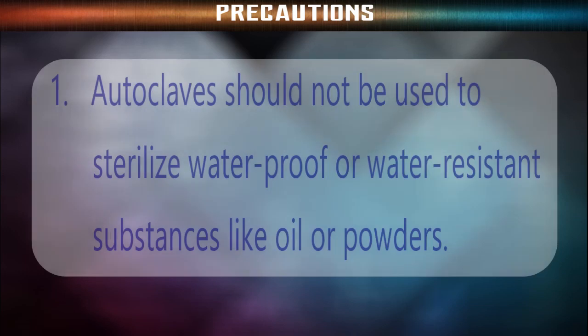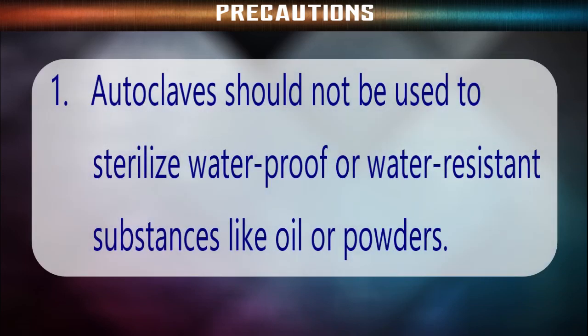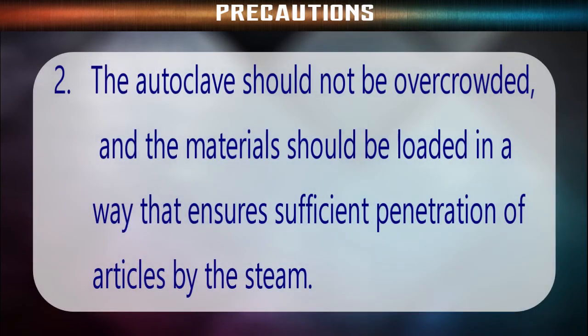Precautions of the autoclave are: although autoclaves are pretty simple to use, there are certain rules and precautions to be followed while operating an autoclave. Some of the important precautions to be followed while running the autoclave are: first, the autoclave should not be used to sterilize waterproof or water-resistant substances like oil or powders. Second, the autoclave should not be overcrowded and the materials should be loaded in a way that ensures sufficient penetration of articles by the steam.